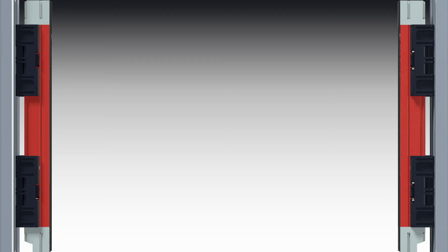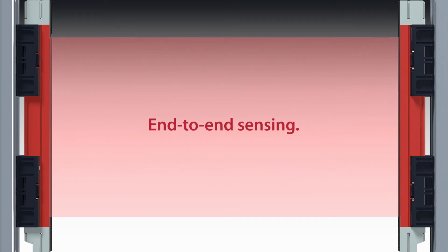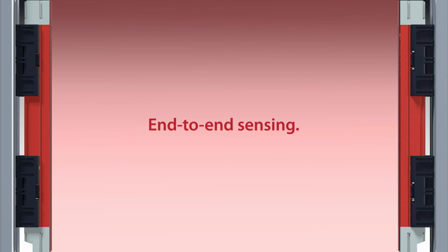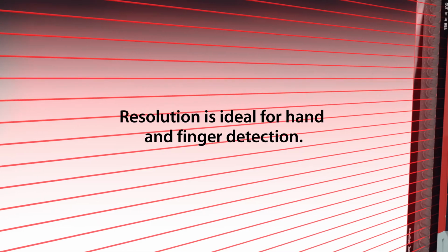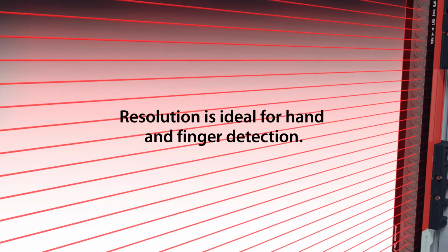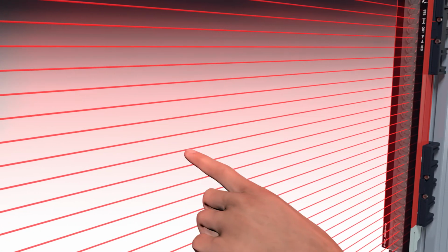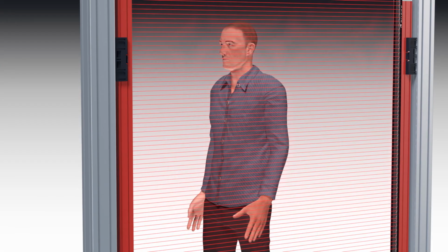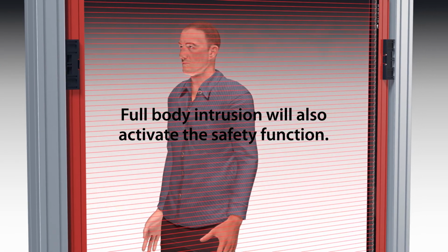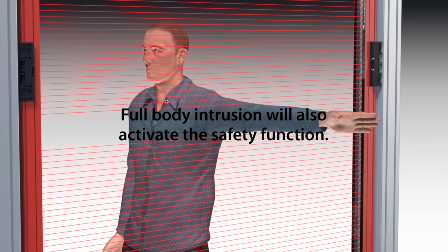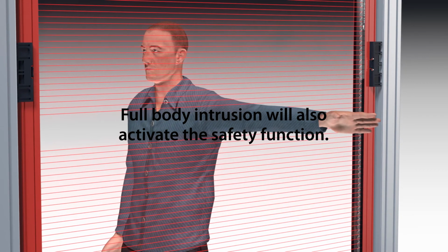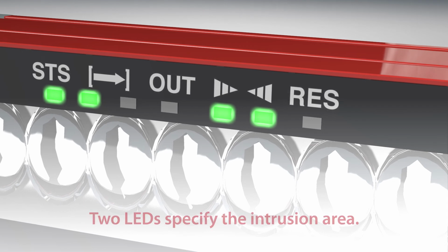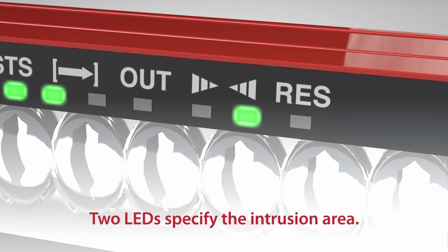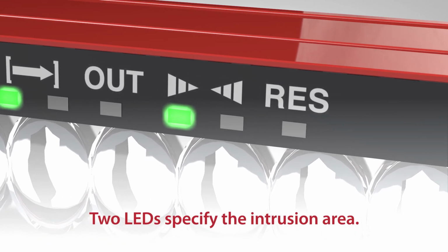The new light curtain protective field provides end-to-end sensing across the entire length of the transceiver. It provides full coverage and mitigates any inactive sensing areas. Its range of resolution is ideal for hand and finger detection. Depending on the resolution of the installed 450L-B transceivers, any interruption of finger, hand, or body will be detected and will activate the safety function. Two LEDs will specify the group of beams of the intrusion to simplify troubleshooting.